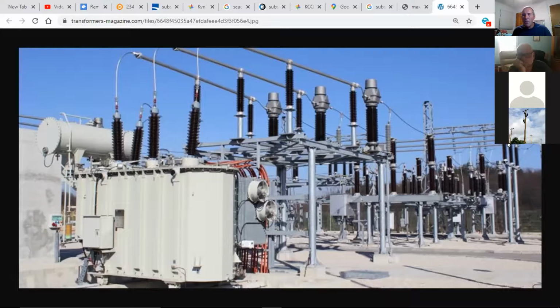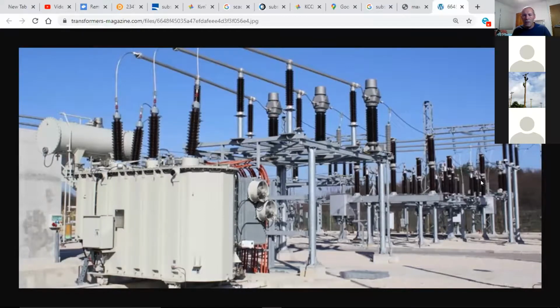Because there's no change in the current? Right, but where can I get a current reading from that encompasses the whole bus? The inbound. After I go through the bus, where do I go to? A breaker, and the breaker goes out to the feeder, correct? Am I getting an amp reading per phase on the breaker? Yeah. You are. So what's going on in this process right here?